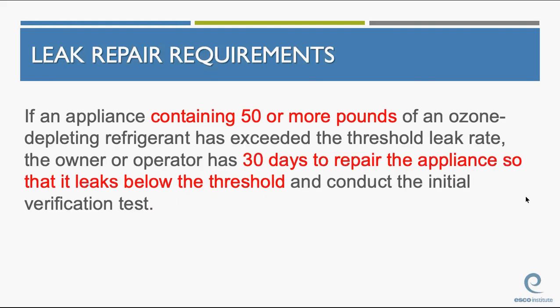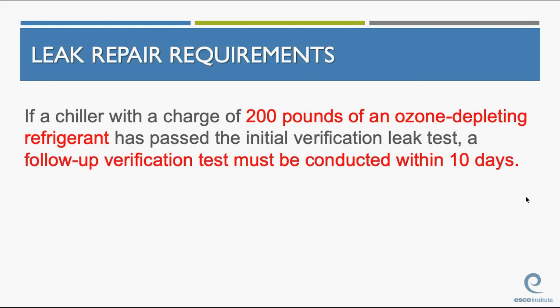If an appliance containing 50 or more pounds of an ozone-depleting refrigerant has exceeded the threshold leak rate, the owner or operator has 30 days to repair the appliance so that it leaks below the threshold and conduct the initial verification test. If a chiller with 200 or more pounds of ozone-depleting refrigerant has passed the initial verification test, a follow-up test has to be conducted within 10 days. Folks, these are the same requirements as Type 2. There's nothing different here. If it's over 200 pounds, we do an initial test and there has to be a follow-up test completed afterwards.